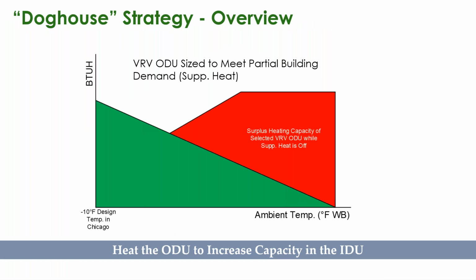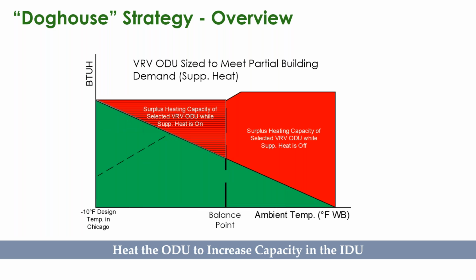Balance is slightly different when you're doing a doghouse strategy. You're heating the outdoor unit to increase the capacity of the indoor unit. And your balance point is not actually the intersection, but where the capacity curve of the variable refrigerant system equipment correlates to your actual design load.